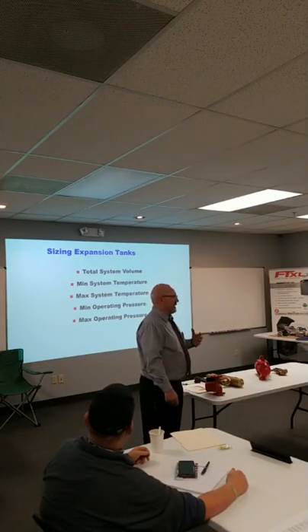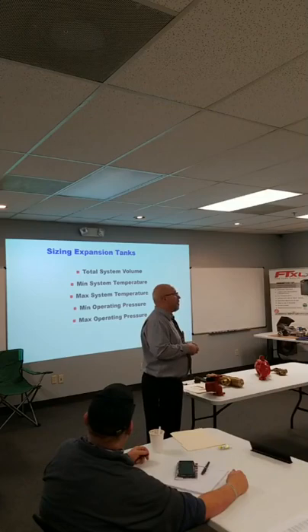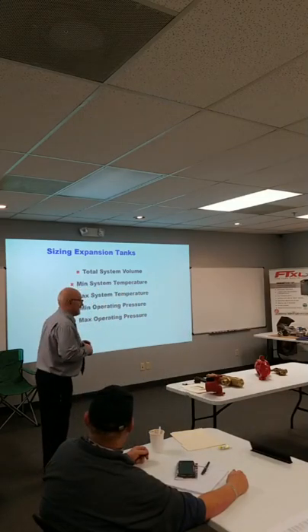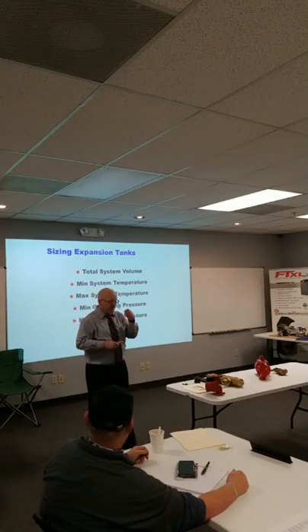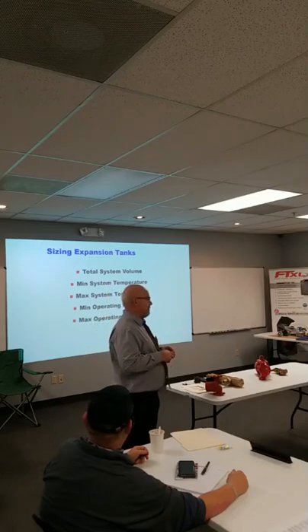If you're just going to say I've got 200 suites in an apartment building or something, that doesn't help me. Or you tell me I've got 2 million BTUs. What expansion tank do I need? The biggest one I've got. I'm going to make some good money. Oversizing an expansion tank isn't going to hurt me, but undersizing will kill me.